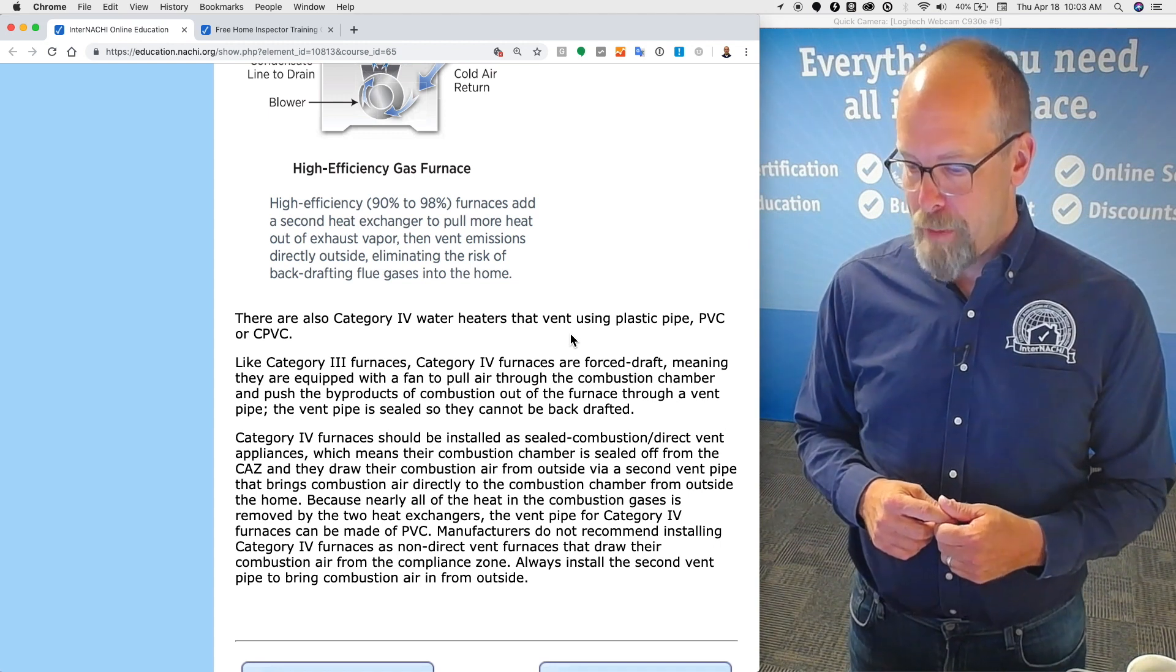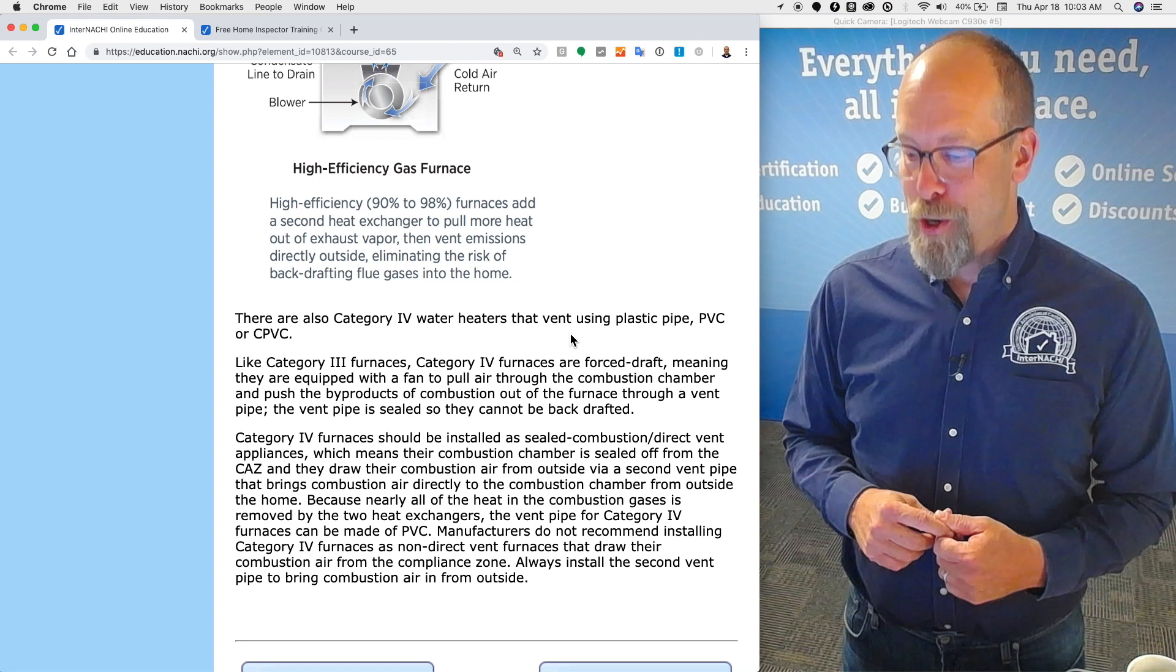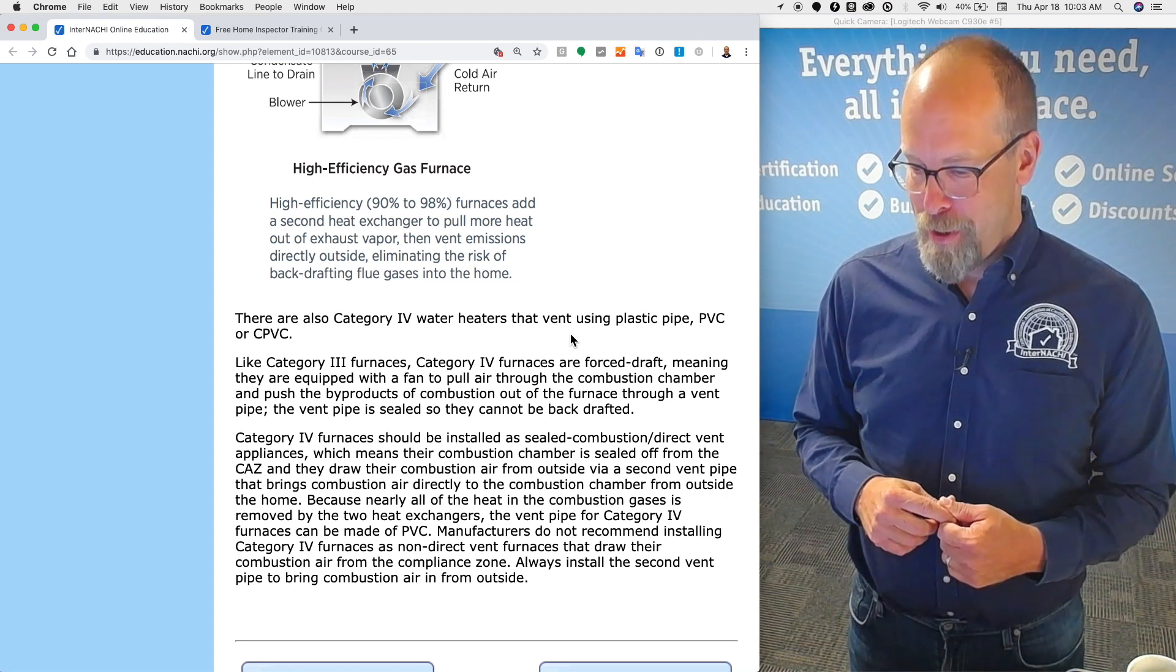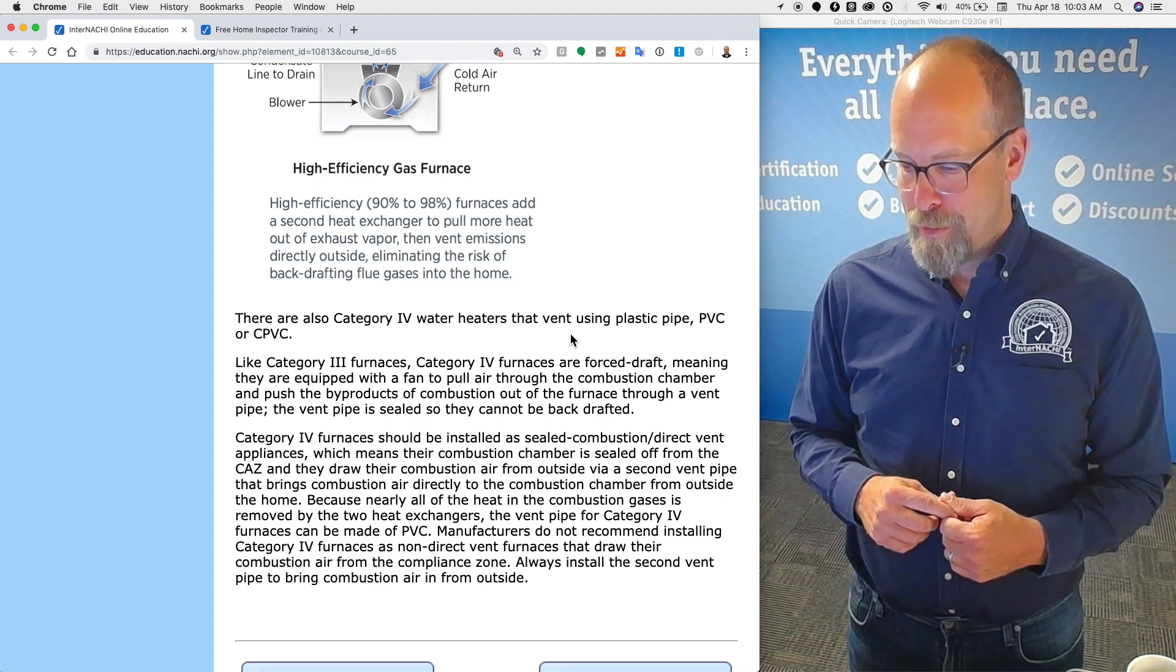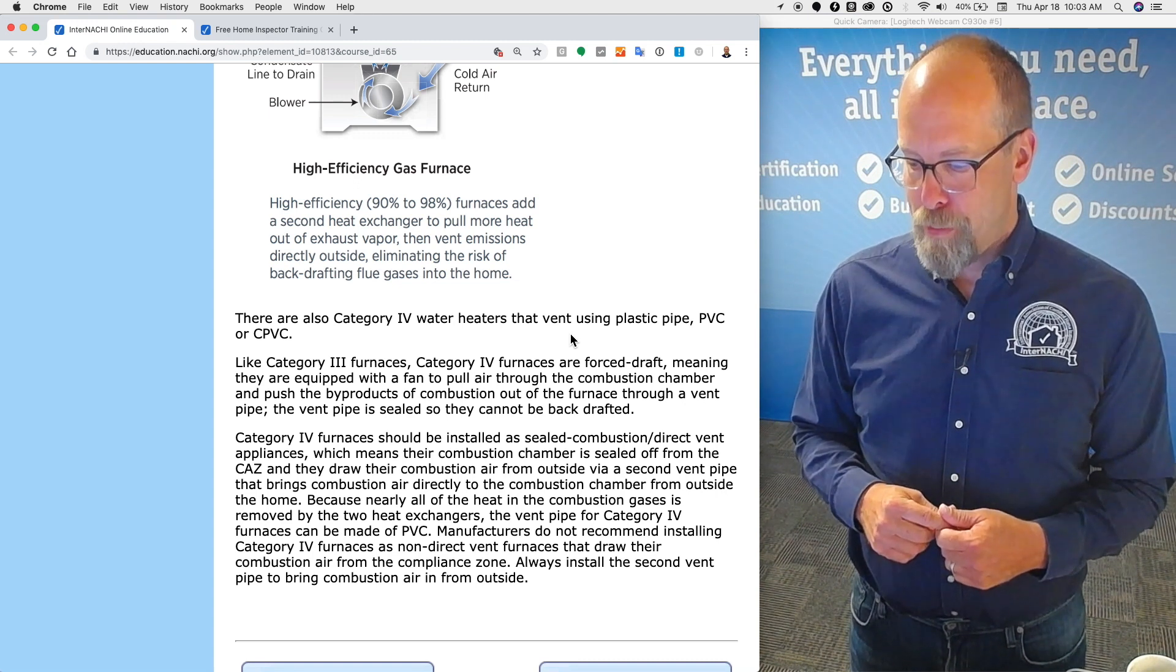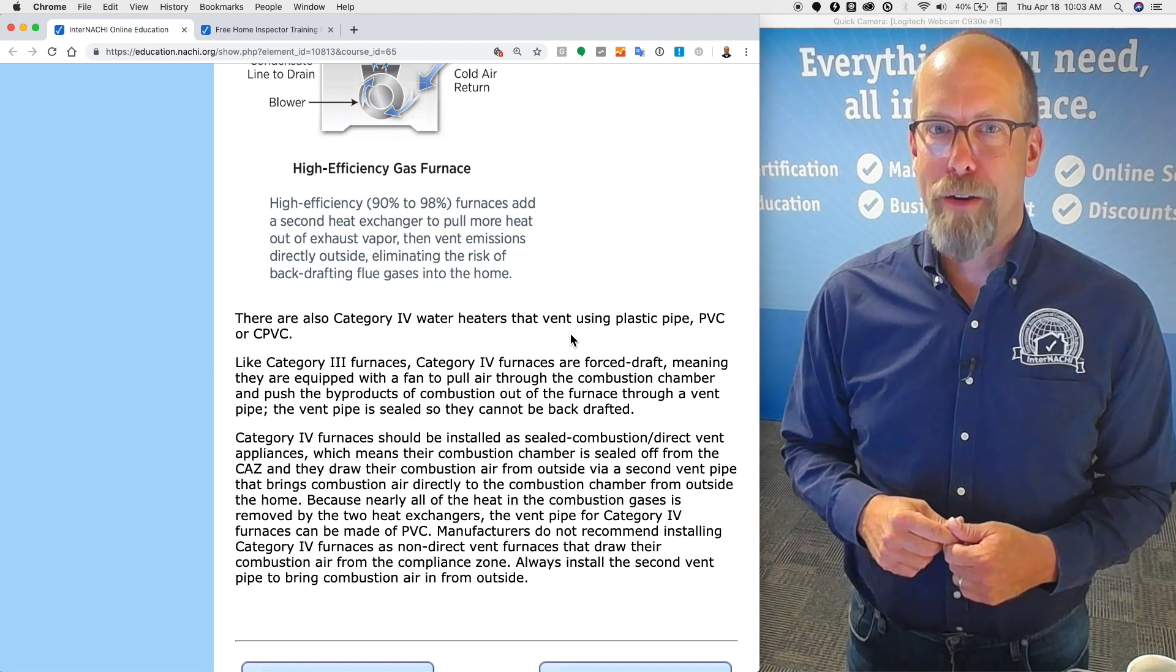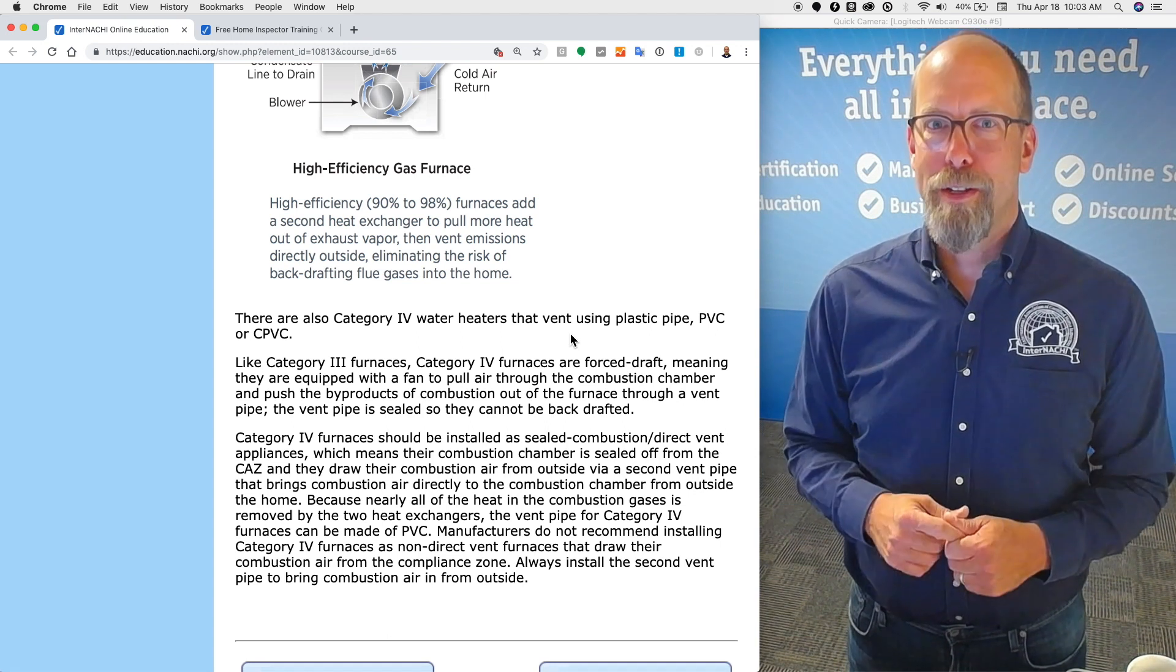Manufacturers do not recommend installing category four furnaces as non-direct vent furnaces that draw their combustion air from the compliance zone. Always install the second vent pipe to bring combustion air from the outside, right into the combustion chamber. It's an all-sealed chamber.